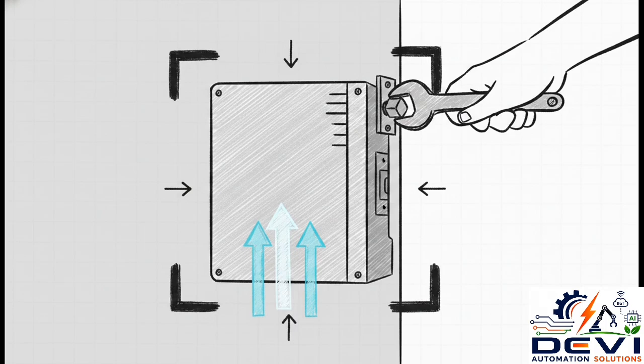If you bake it in the sun or let it choke on factory dust, its lifespan is going to plummet. When you're actually mounting the thing, whether you're wall mounting, panel mounting, or snapping a smaller drive onto a DIN rail, there is one non-negotiable rule: cooling space. You literally cannot suffocate the drive by packing it too tightly next to other components. You must ensure adequate mounting distance around the unit. Always verify the fan airflow direction so you aren't blowing hot air directly into another sensitive device. And of course, ensure your fastening is completely secure to withstand any environmental vibration.